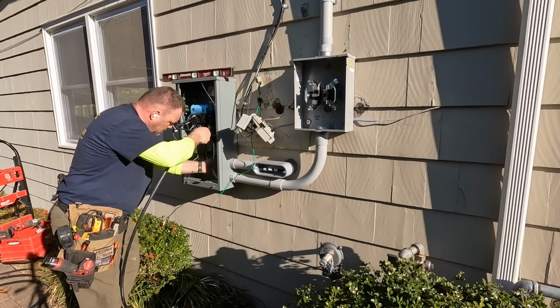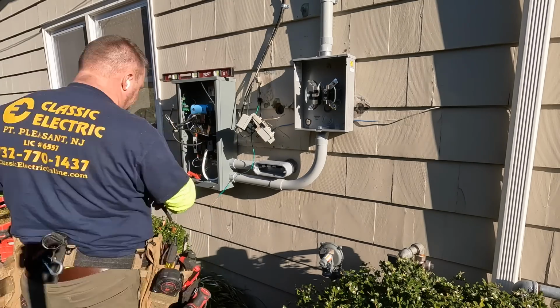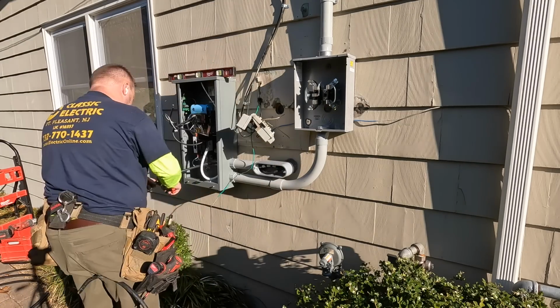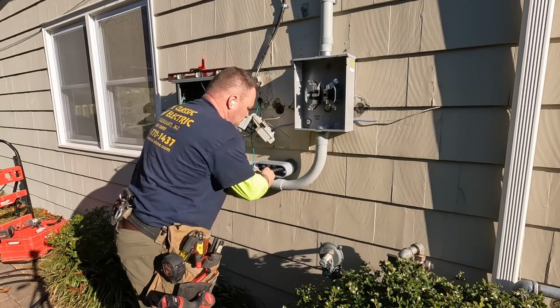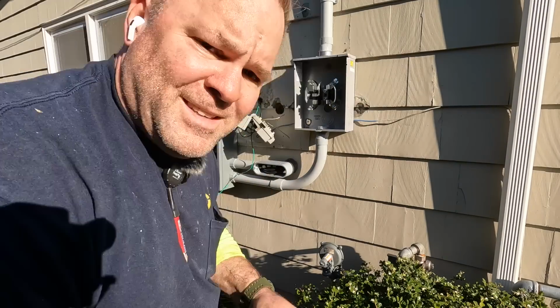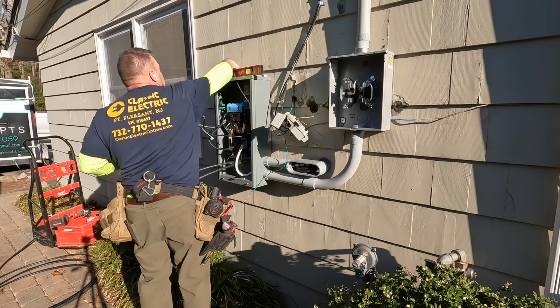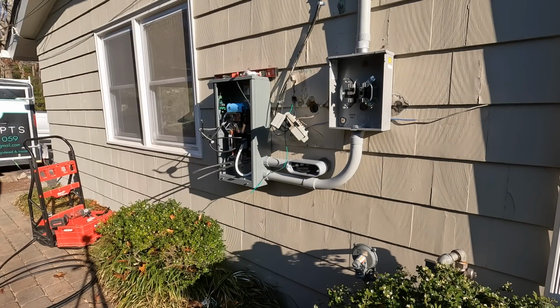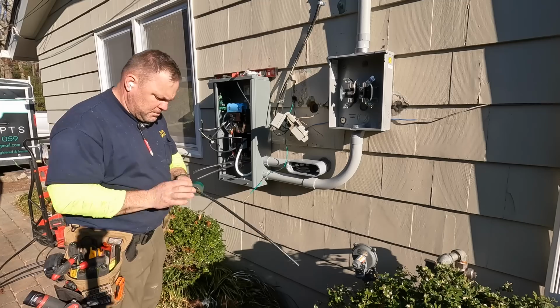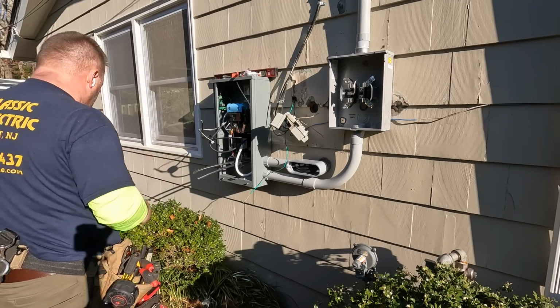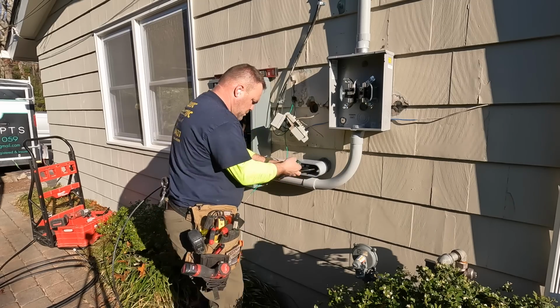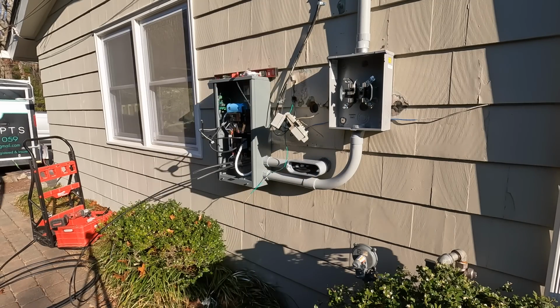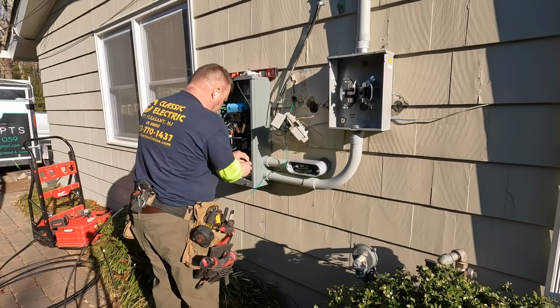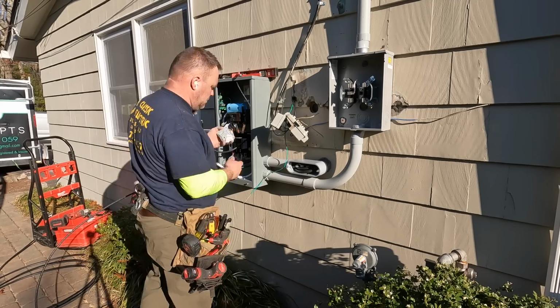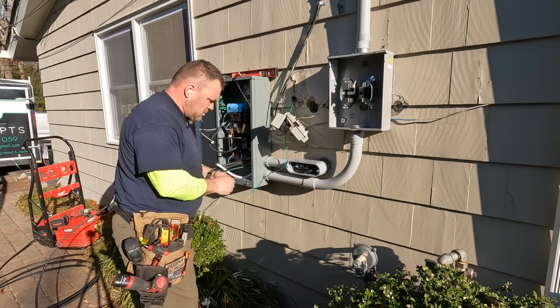All right, so here I am wiring the load side of the terminals inside the transfer switch, which goes inside to the panel where all the circuit breakers are. And this took a little bit of time. I did do the research on box fill or conduit fill on this 2-inch PVC, and I am allowed to use 3 pieces of 4/0 aluminum and 1 piece of number 2 aluminum for the equipment grounding conductor. That's just below the maximum fill for this conduit, using Chapter 9, Tables 1, 4, and 5 to figure that out.